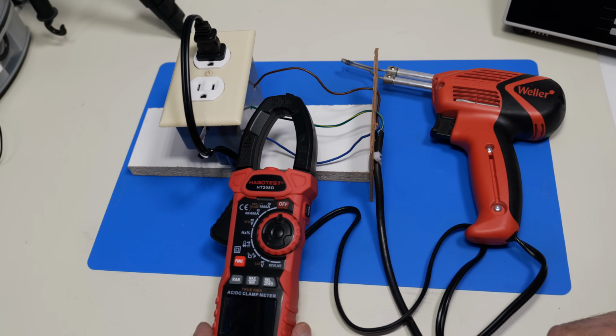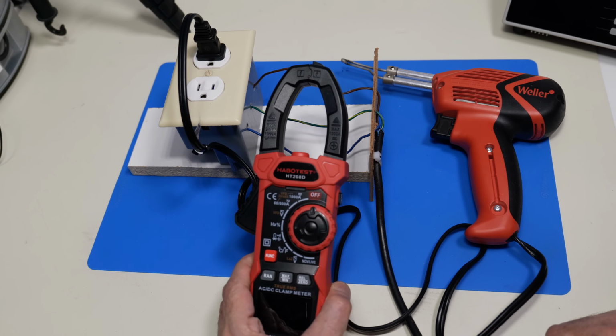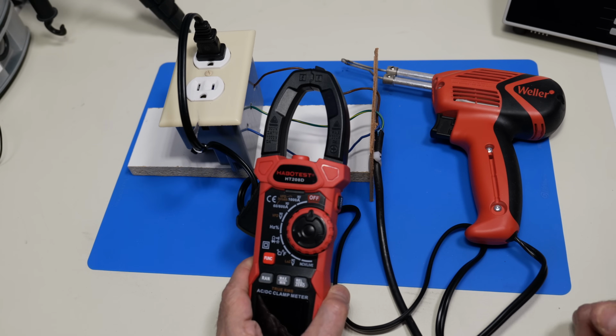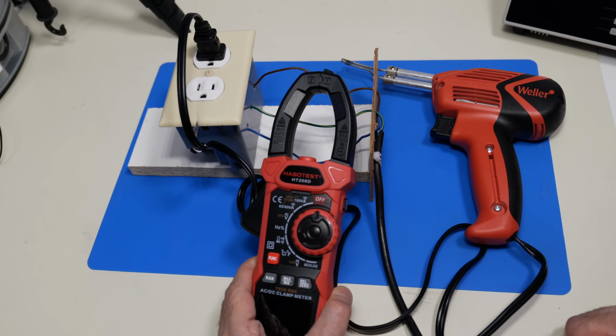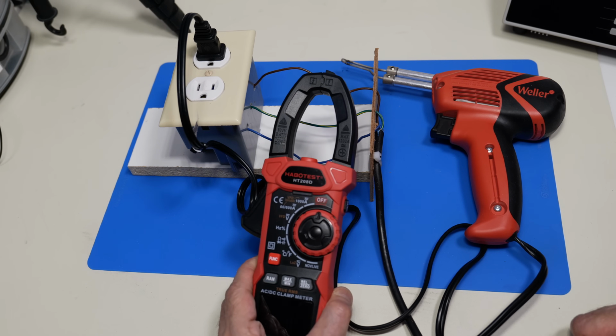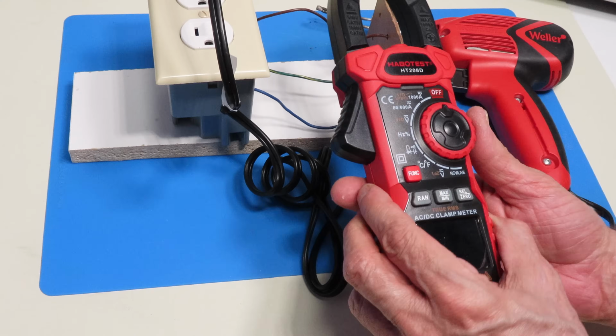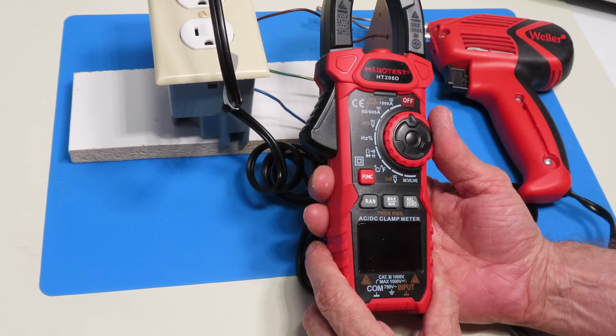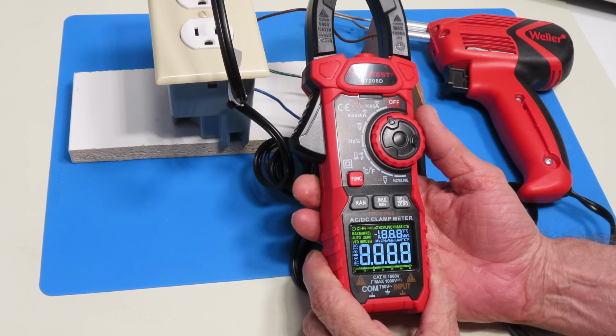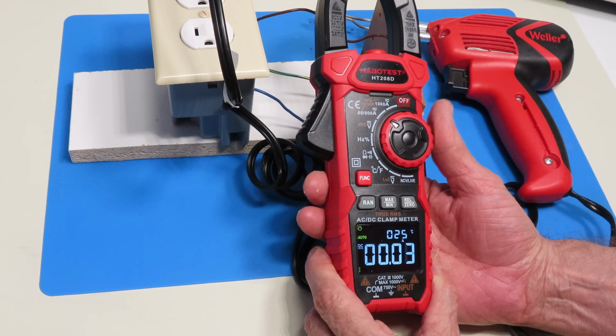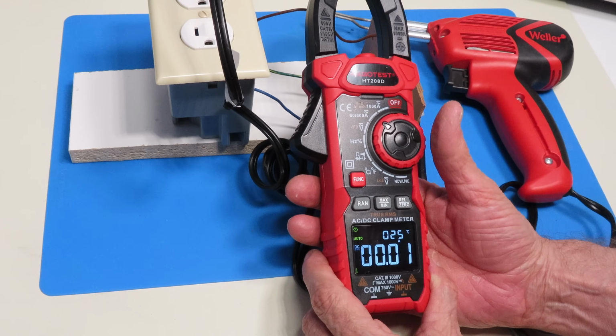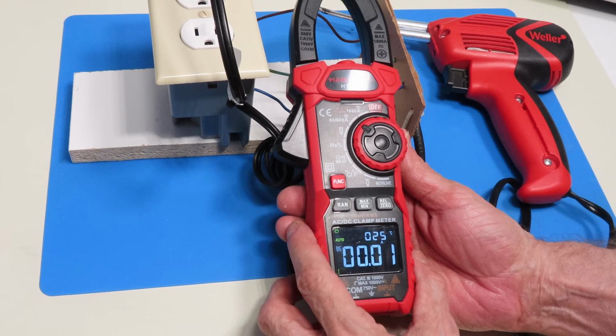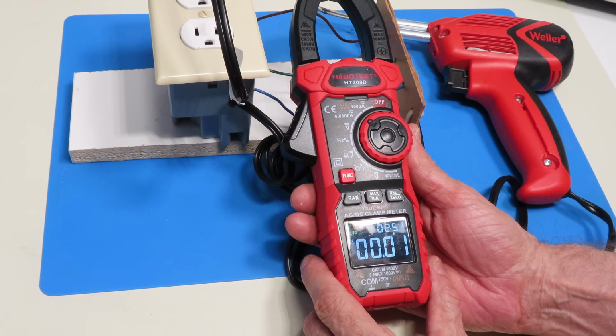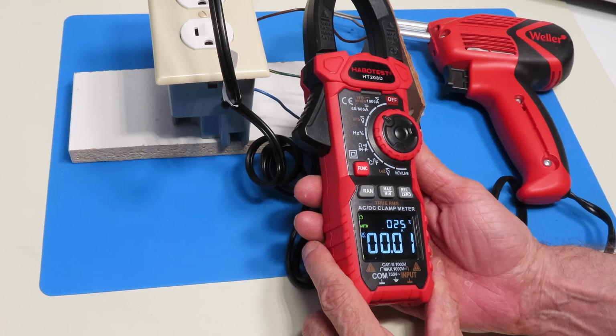In this demonstration, we're going to use the clamping meter to do an inductive current test. This is great to be able to do because measuring AC current, especially high AC current, can be somewhat dangerous, so not having to actually contact the wires is a good thing. I'll put this into current mode - I've got two of them, a high current mode up to 1,000 amps and a lower one at 60 or 600 amps. These currents are normally for fairly high currents - you're not going to be measuring milliamps with them.